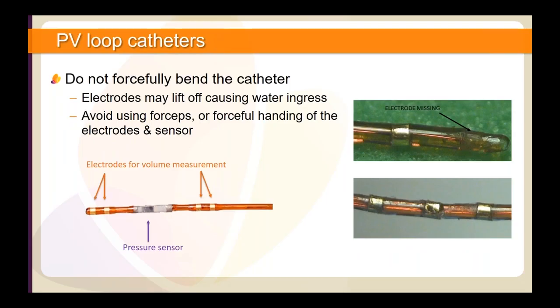None of our catheters should be forcefully bent, but the PV catheters have a longer segment which is relatively stiff due to the presence of the volume electrodes. Bending of this section of the catheter may damage the electrode connections or cause the electrodes to lift off, allowing fluid to seep in. Much like the pressure sensors, the volume electrodes should be treated with care, and it is best not to handle the catheter in this area.